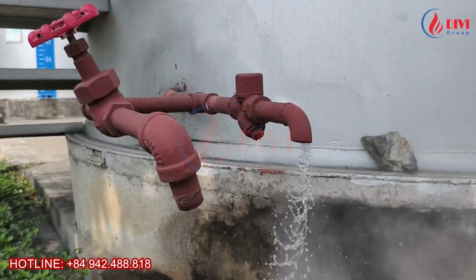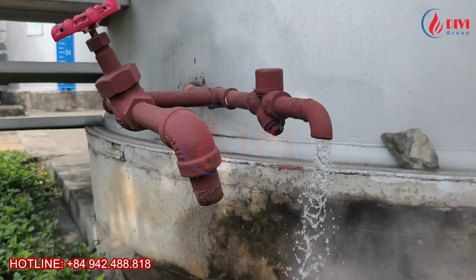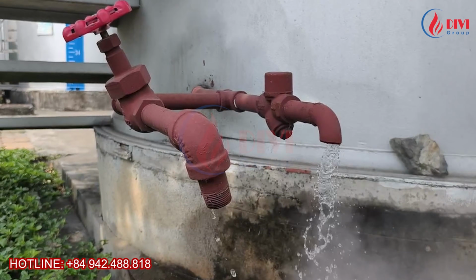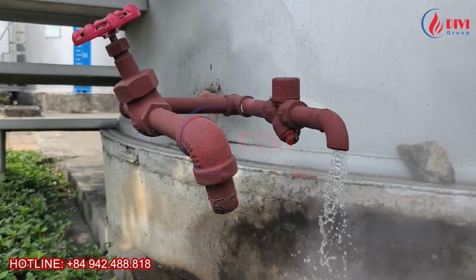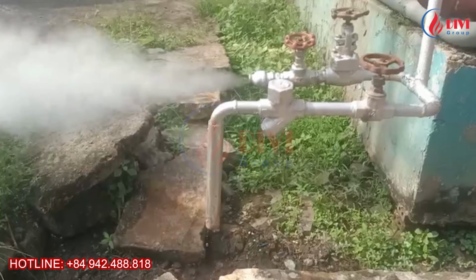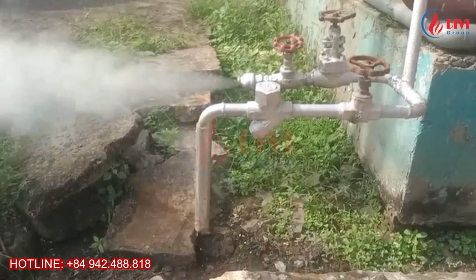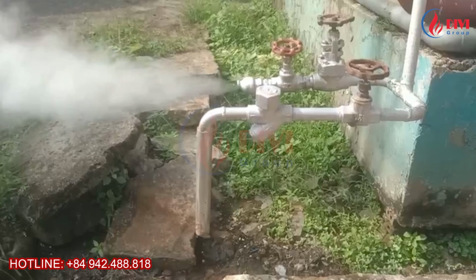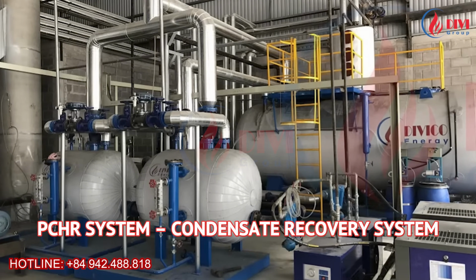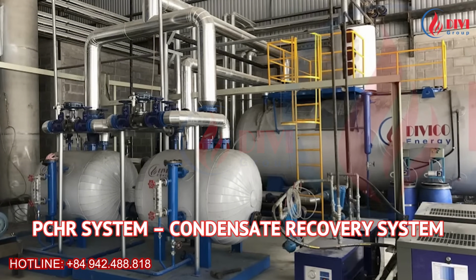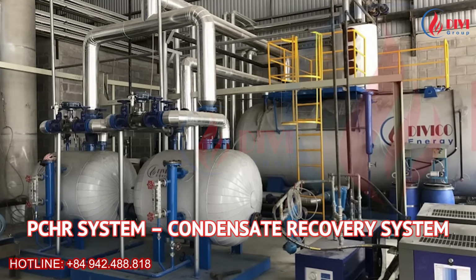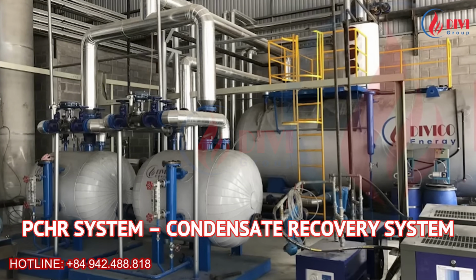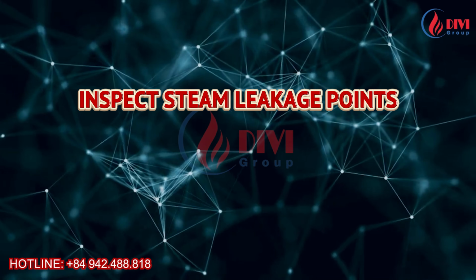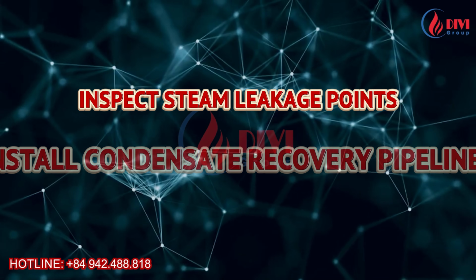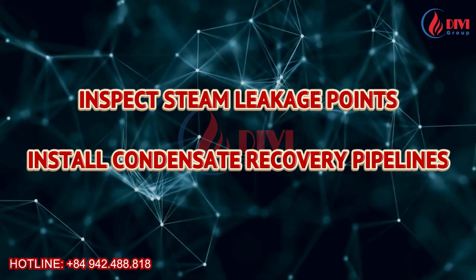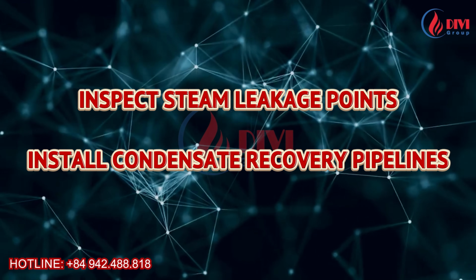Another common issue is that many production lines discharge condensate without recovering it back to the boiler system. Many factories believe that investing in a condensate recovery system is not worth the cost. But when calculated over months, years, or the entire lifetime of the factory, condensate recovery becomes an extremely valuable investment. The solution is actually quite simple. Regularly inspect steam leaks and repair them immediately, install condensate recovery pipelines, and return the condensate back to the boiler system.